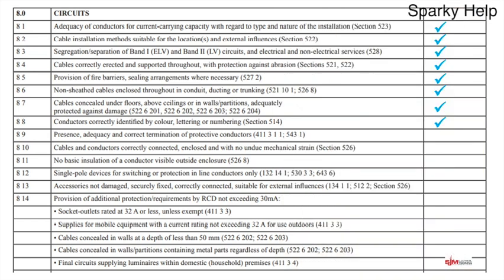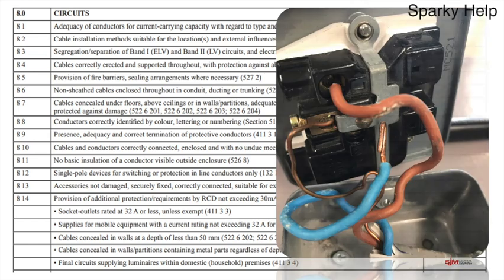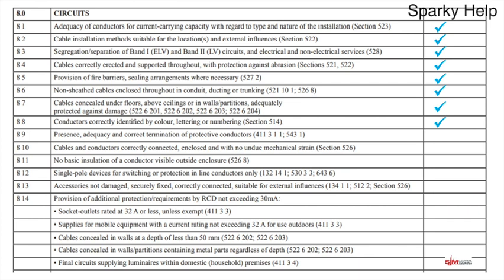Presence, adequacy, and correct termination of protective conductors. Is it correctly connected? Does it meet the requirements? There's a loose connection there, and also there's no sleeving on the actual CPC, so that would need looking at. But hopefully if you went round and rectified it, it would be okay.